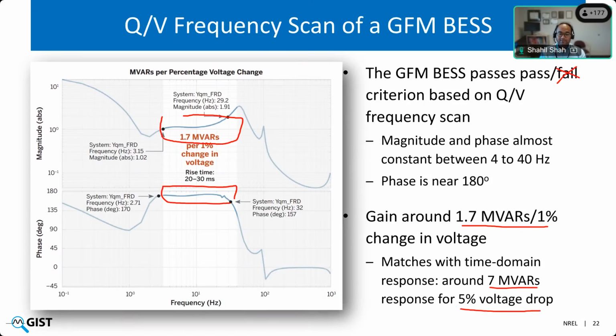So it's just the frequency of perturbation in the input variable, which in Q by V scan is voltage magnitude. In P by theta scan, it's the voltage phase angle. In V by I impedance scan, it's actually positive sequence perturbation. So it's not voltage magnitude or angle, but more like an additive perturbation. It depends on which transfer function you are using. We haven't used DQ admittance or DQ matrix in this particular case, but it is possible to use that as well. Deepak, you want to add anything on this?